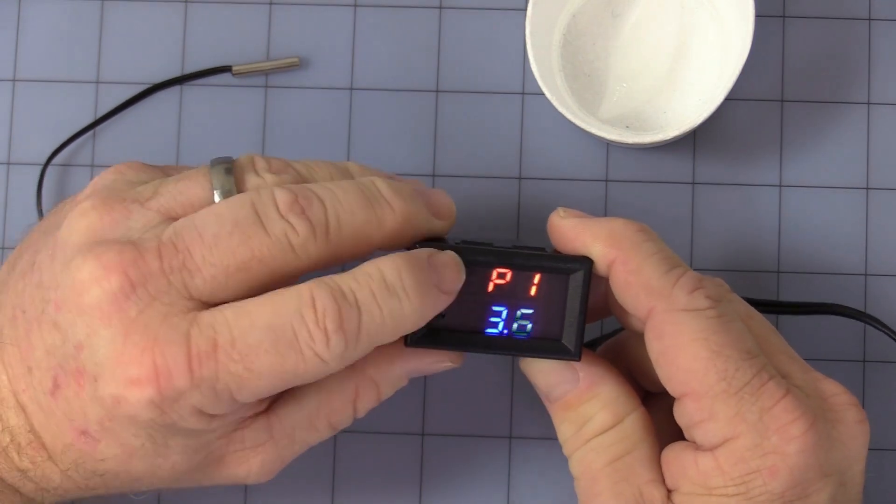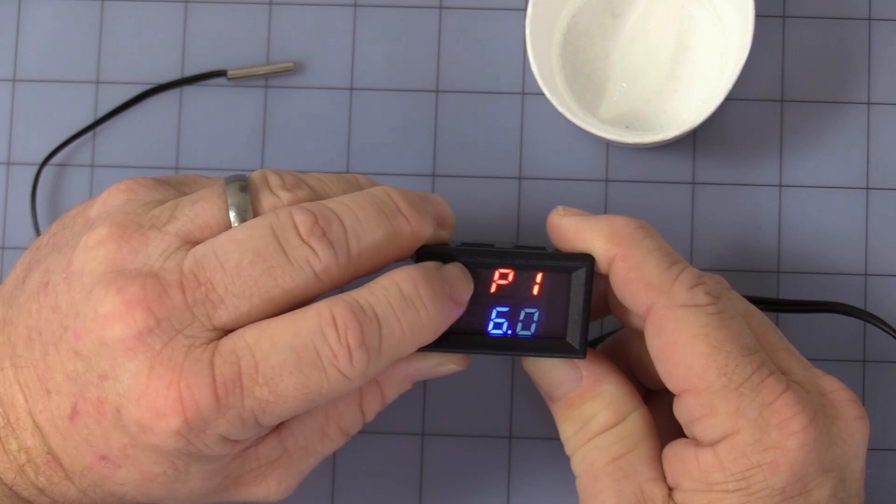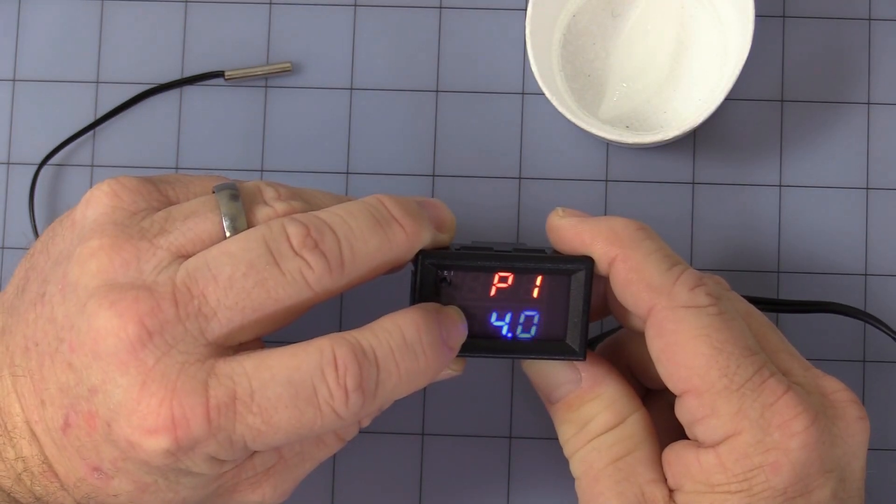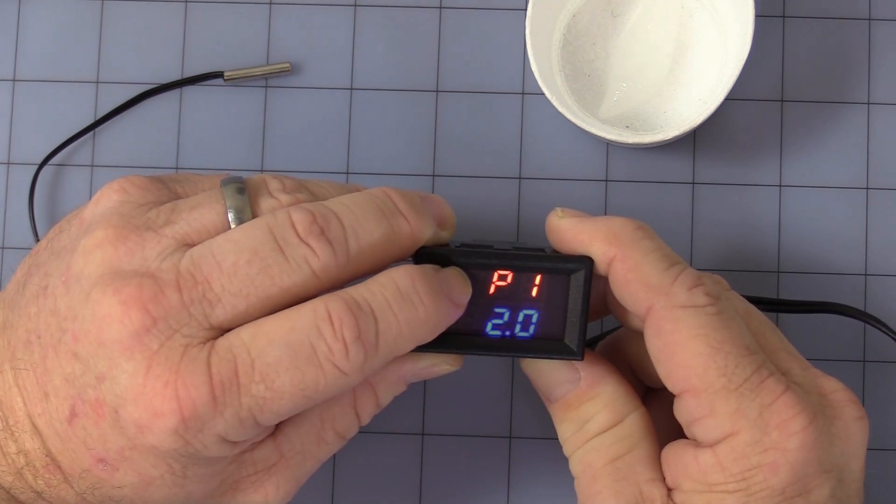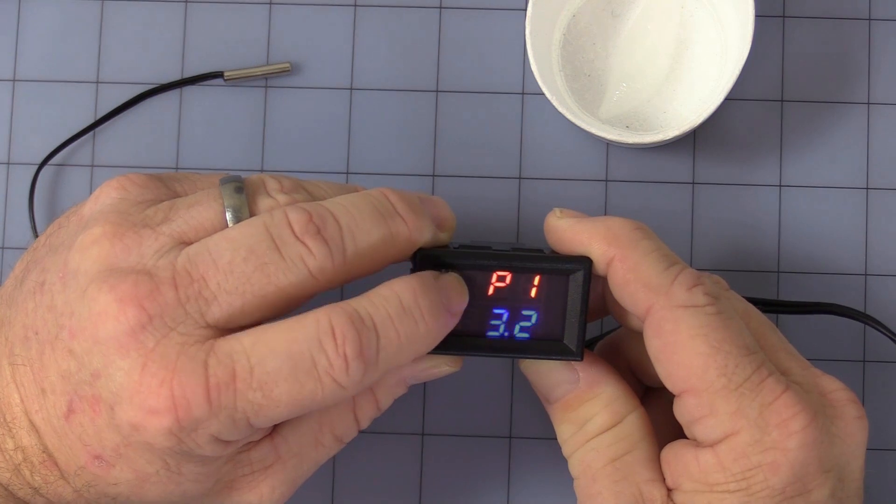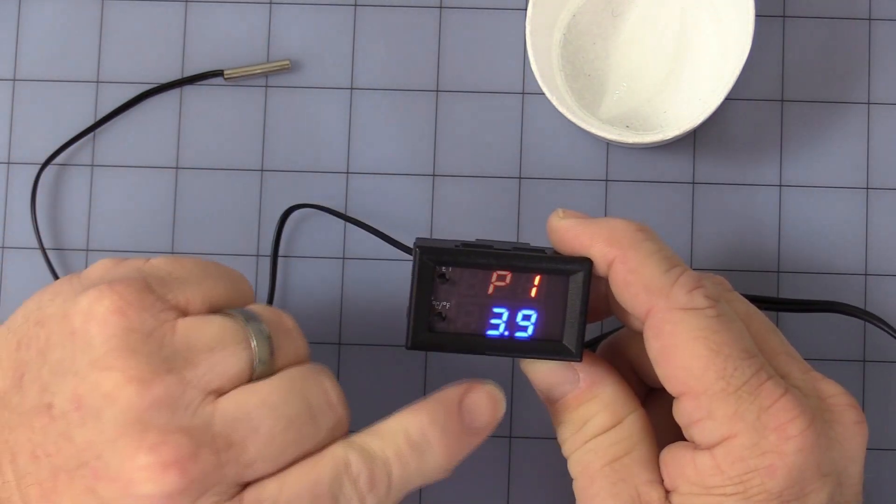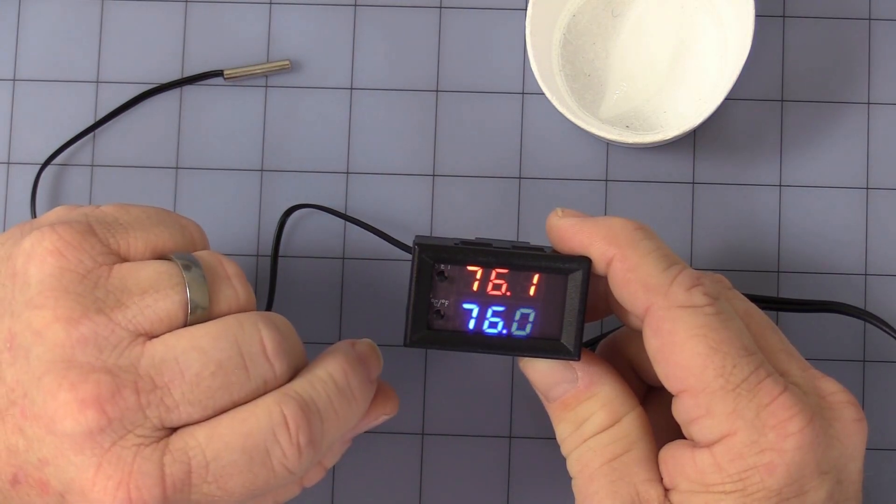There again, press both buttons to enter the program. Once it starts flashing, this is your hysteresis. You can change it from 0.1 to 30 degrees hysteresis. Then, when you get to your set point, just leave it. And when it stops flashing, it will automatically go back into running the program.